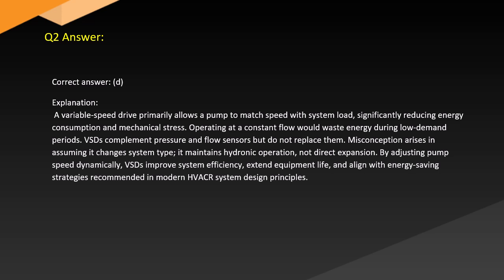A variable speed drive primarily allows a pump to match speed with system load, significantly reducing energy consumption and mechanical stress. Operating at a constant flow would waste energy during low demand periods. VSDs complement pressure and flow sensors but do not replace them. Misconception arises in assuming it changes system type. It maintains hydronic operation, not direct expansion. By adjusting pump speed dynamically, VSDs improve system efficiency, extend equipment life, and align with energy-saving strategies recommended in modern HVACR system design principles.